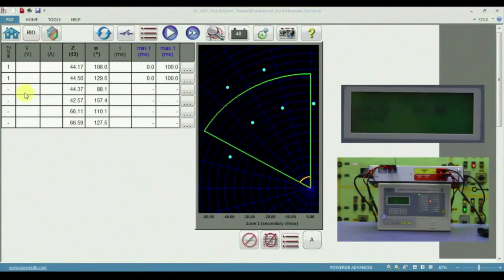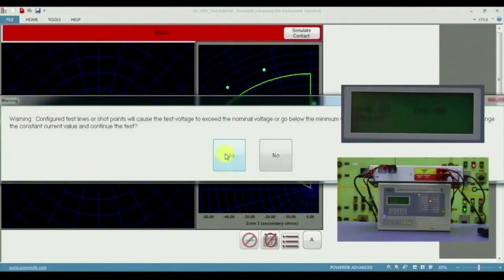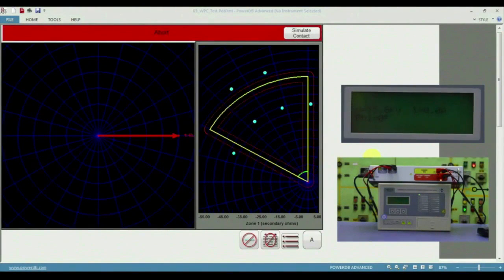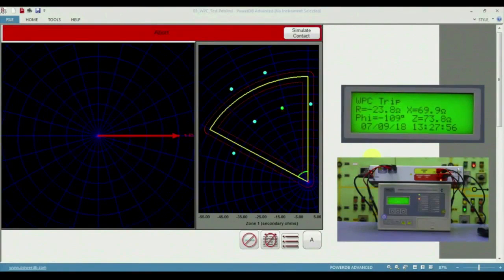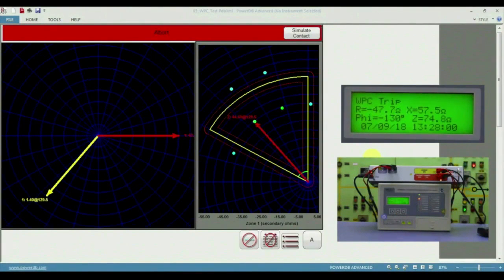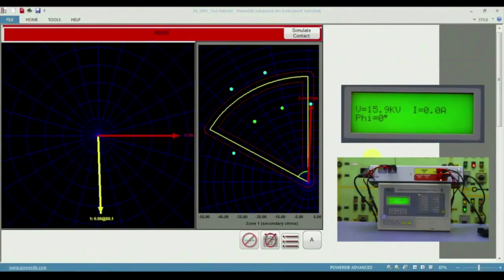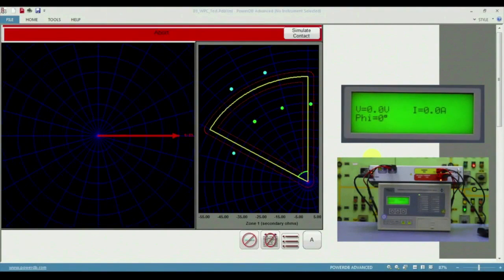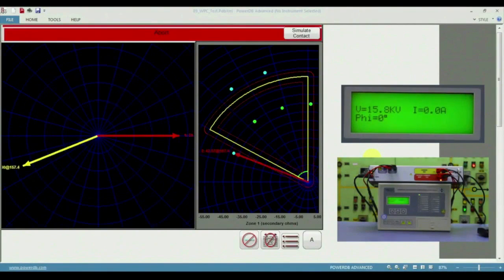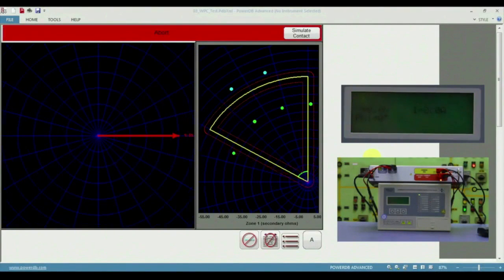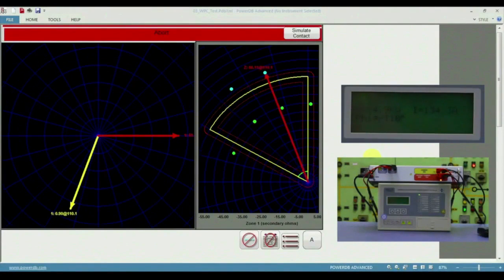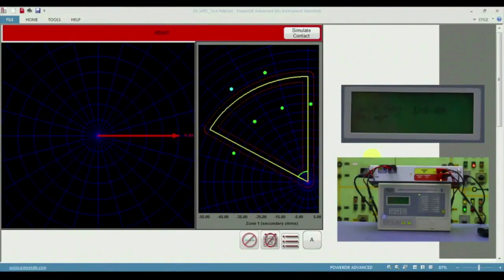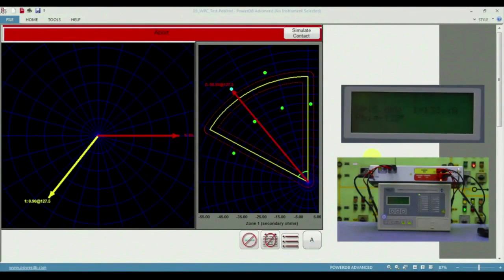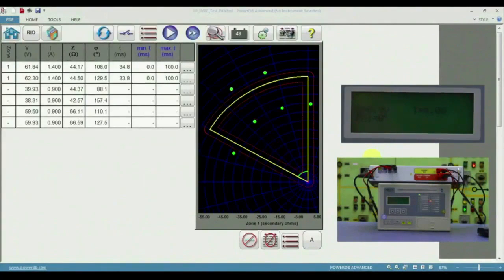Only 2 points are inside, which is going to operate. So let me click on the play button. The first point, there is operation on WPC; second point on WPC; the third point, which is less than 90, there is no operation; the fourth point, more than 150, there is no operation; the fifth point, outside 60 ohms, no operation; and the sixth point, that's also outside 60 ohms, so no operation. So with this we can perfectly identify the region of operation.